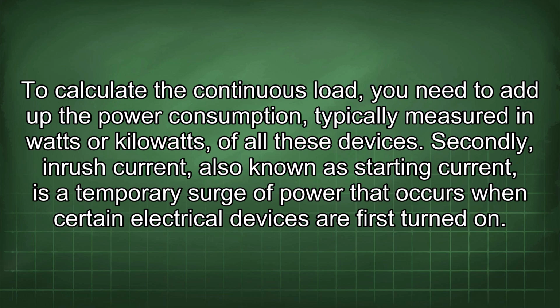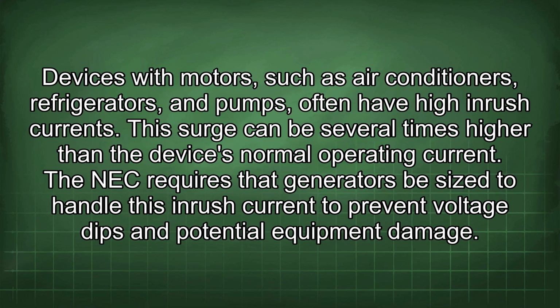Secondly, inrush current, also known as starting current, is a temporary surge of power that occurs when certain electrical devices are first turned on. Devices with motors, such as air conditioners, refrigerators, and pumps, often have high inrush currents. This surge can be several times higher than the device's normal operating current. The NEC requires that generators be sized to handle this inrush current to prevent voltage dips and potential equipment damage.